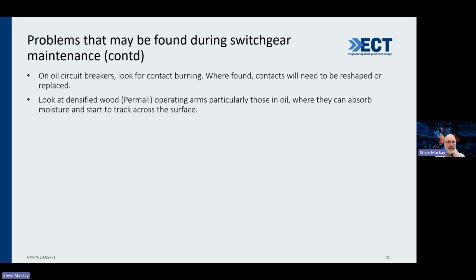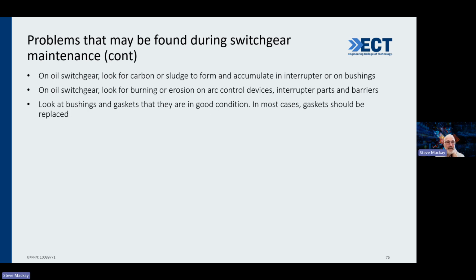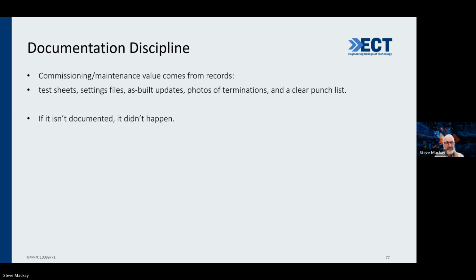So oil can absorb moisture and start to track across the surface. So these are all things you need to look for. And then obviously in oil switchgear, carbon or sludge can form. That's obviously a big issue. And burning or erosion. And these are all issues. And obviously bushings and gaskets, good condition. Don't try and avoid replacing gaskets. If you've got any doubt, replace the gasket. Don't try and ignore the problems there. It's worth fixing it now.